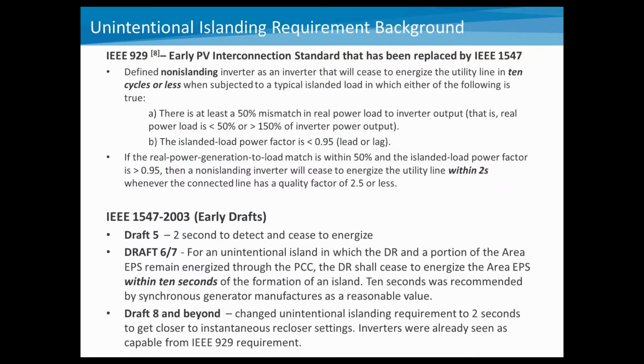I wanted to throw up a little bit of background material on where this requirement came from. Prior to 1547, there was an earlier interconnection standard focused on PV systems called IEEE 929. This has since been withdrawn and replaced by 1547, but if you go back and look at some of the requirements in that document, you can see that they gave a couple of conditions that the inverter must recognize and then disconnect.